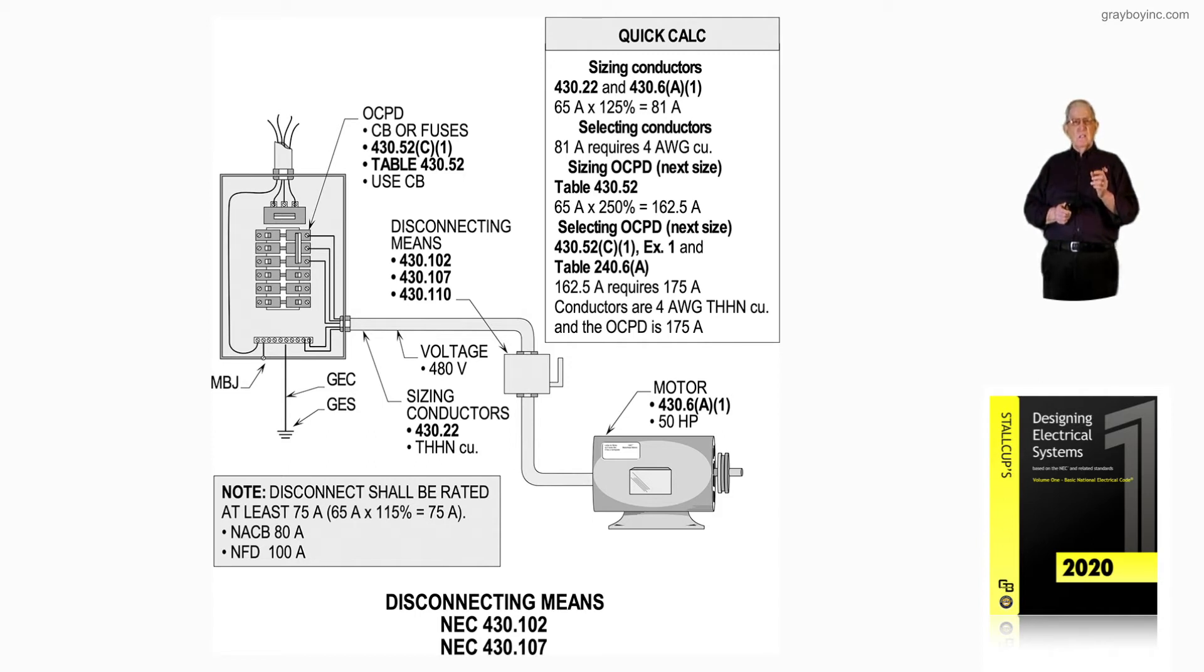Notice the note. It says the disconnect shall be rated at least 75 amps. 65 times 115 percent equals 75. Where do we get that 115 percent? Just go over and look at 430.110A. 75 amps would require a non-automatic circuit breaker at 80 amps or a non-fusible disconnect at 100 amps. Neither has any overcurrent characteristics. It'd be mostly like a single-pole switch.